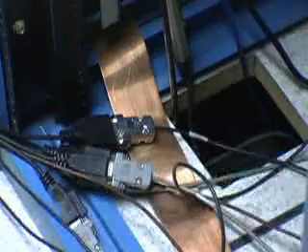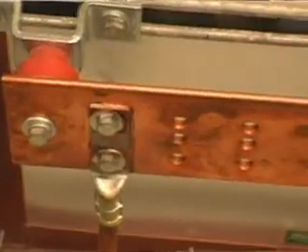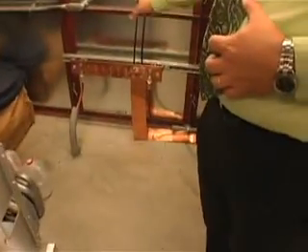A lot of the manufacturers only have specifications of electrical cord grounding, but we try to make sure all of our racks are still, again, tied into the electrical ground as well as the outside loop ground. What we have is a grounding bar that is the central tie point for all the electrical equipment, for the electrical service, out to the grounding ring that is tied to the deep ground.